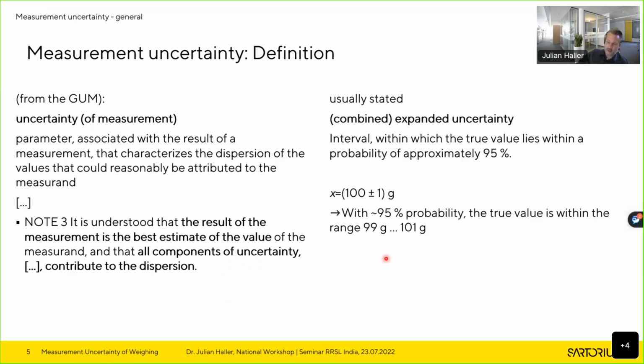What is usually stated by convention is the so-called combined expanded uncertainty. Practically, it's an interval within which the true value lies with a probability of approximately 95%. And it is usually stated as that. So you have any measurement result, for example, 100 gram, with an uncertainty of 1 gram, and then it can be stated like this. And this just means with 95% probability, the true value is within the range 100 minus 1 gram, 99 gram, to 100 plus 1 gram, 101 gram.